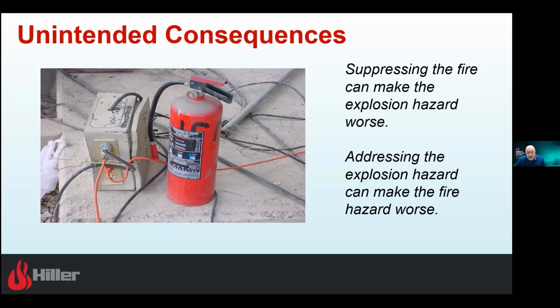We have 3 options. We can do an NFPA 69 approach, which says let's get rid of the gas at the onset, open it up, run air through there and move that gas out so that we do not get an ignition. The second option is an NFPA 68 application. What that means is, okay, the gas is going to build up and we're going to allow it to explode or potentially explode, and we're going to try to mitigate the pressure wave, letting it out through openings in the container or cabinet through deflagration panels.